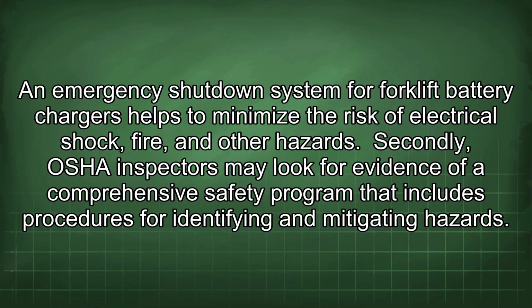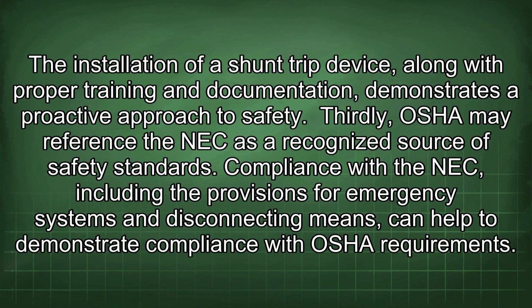Secondly, OSHA inspectors may look for evidence of a comprehensive safety program that includes procedures for identifying and mitigating hazards. The installation of a shunt trip device, along with proper training and documentation, demonstrates a proactive approach to safety. Thirdly, OSHA may reference the NEC as a recognized source of safety standards. Compliance with the NEC, including the provisions for emergency systems and disconnecting means, can help to demonstrate compliance with OSHA requirements.